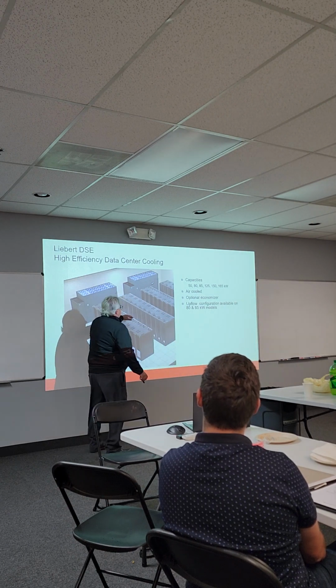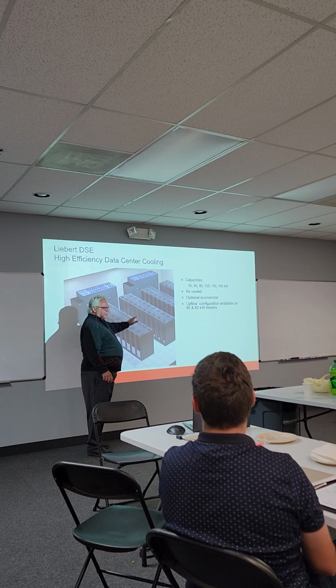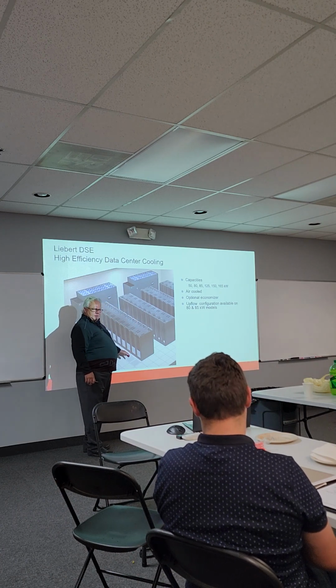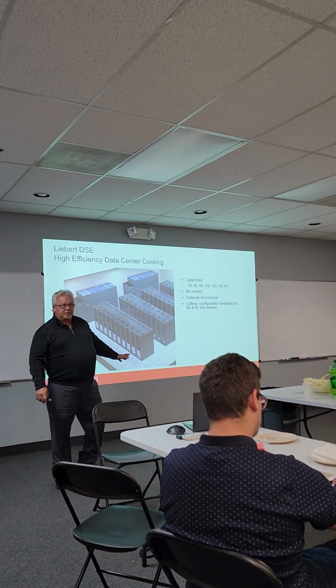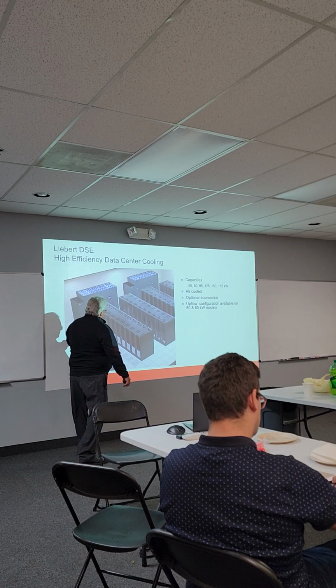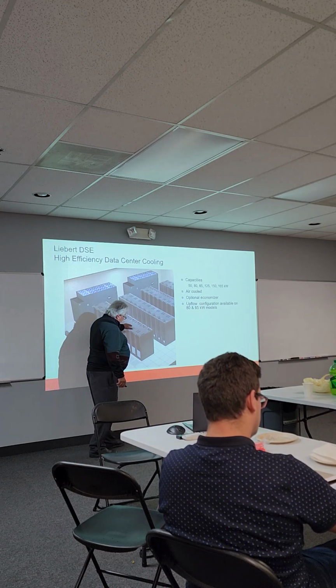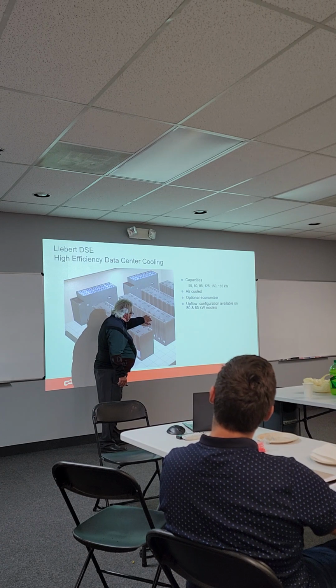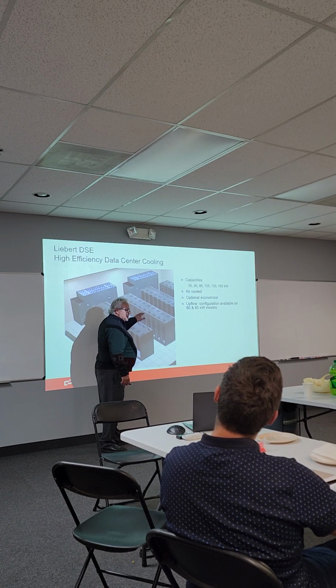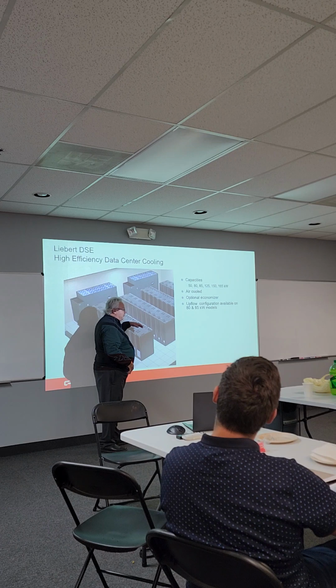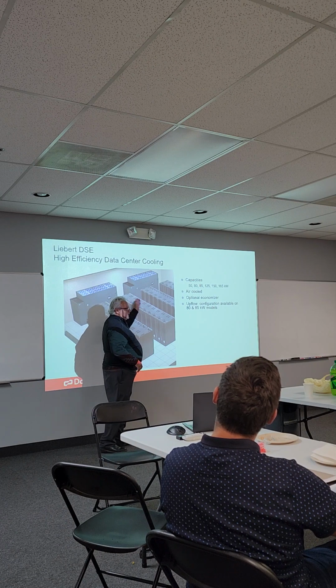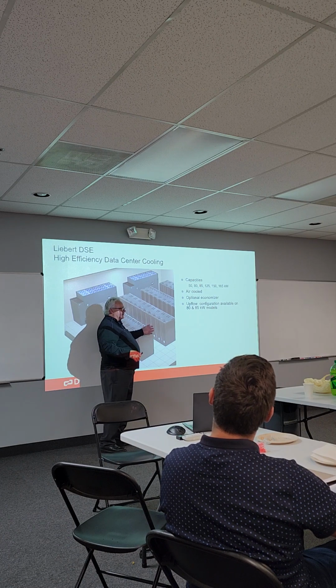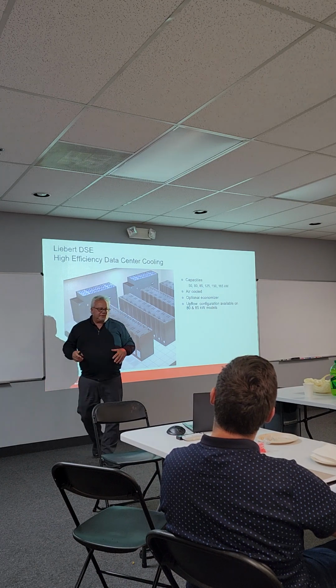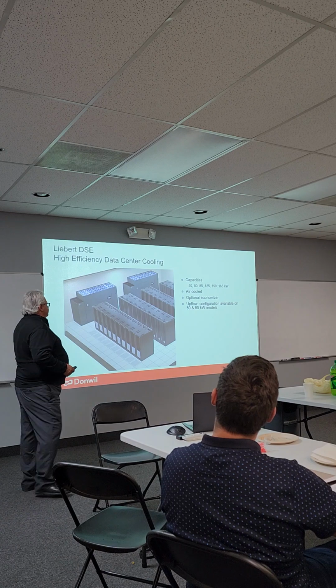Alright, so hot aisle, cold aisle. Remember that if you go into a computer room, try to identify this and see if they have it set up properly. If not, a lot of times you'll see a unit bringing in cold air and exhausting hot air, but the racks are configured wrong, so one unit blows cold air while hot air goes out, and another ends up sucking in hot air instead of cold. Then they can't keep their equipment cold and say, I can't keep my servers cold. There are all kinds of little things like this to look for when you go into a computer room.